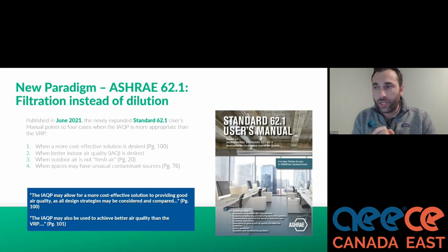So one of the scenarios in which the IAQp may be more appropriate to use than ventilation is when a more cost-effective solution is desired. The other is when better indoor air quality is desired, or when outdoor air is not fresh. Let's say you're in an urban environment where the outside air louvers are next to a major roadway or next to an airport. I look at these 4 items and say, well, geez, these apply to pretty much every building, right? Show number 1 to a developer, show number 2 to a tenant, and show number 3 to anybody out on the street during wildfire season or in a major metropolitan area.